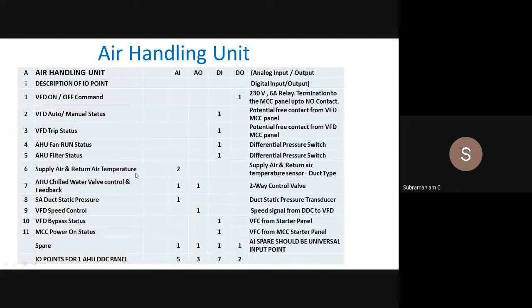Supply and return air is analog. This is coming as an input to the DDC controller. So this is input. Chilled water control: whatever is control will go as output, analog output. Feedback: for my valve, I want to know what position it is in. That static pressure sensor, this one. VFD speed control is output. Bypass is digital input. Power on status. Like that you add them together. You are getting, for example, here including spare: 5 analog inputs, 3 analog outputs, 7 digital inputs, 2 digital outputs.